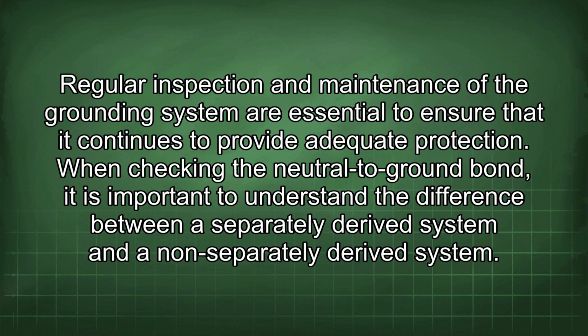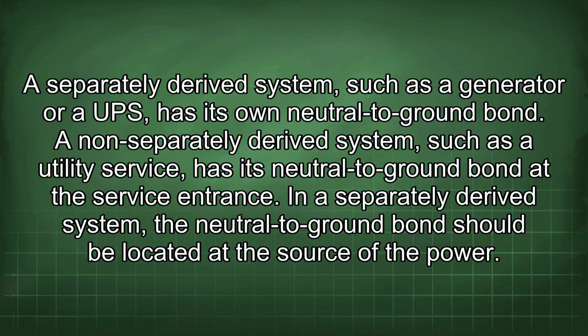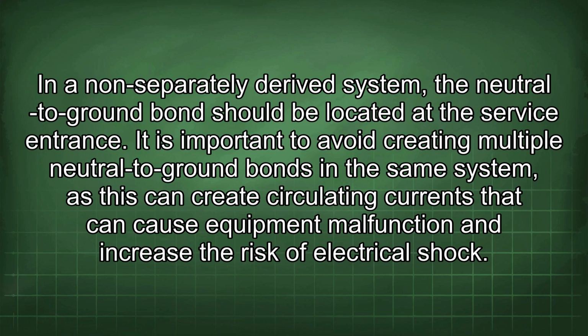When checking the neutral to ground bond, it is important to understand the difference between a separately derived system and a non-separately derived system. A separately derived system, such as a generator or a UPS, has its own neutral to ground bond. A non-separately derived system, such as a utility service, has its neutral to ground bond at the service entrance. In a separately derived system, the neutral to ground bond should be located at the source of the power. In a non-separately derived system, the neutral to ground bond should be located at the service entrance.